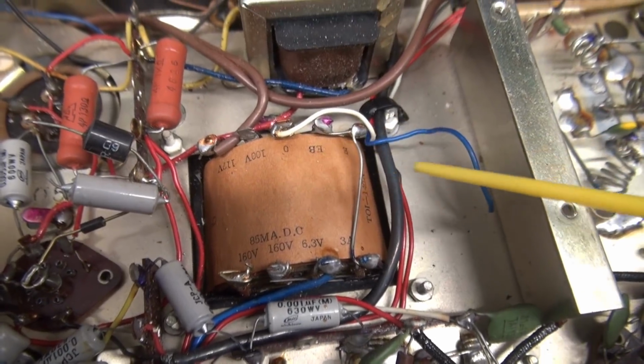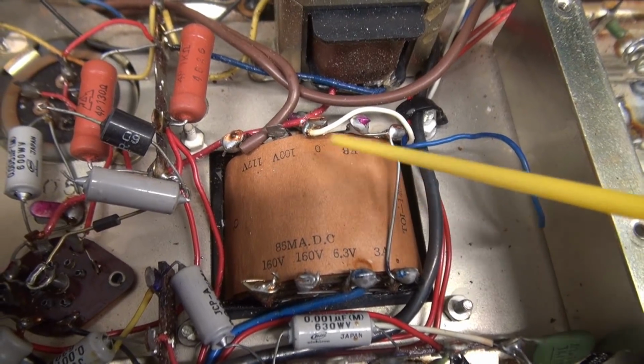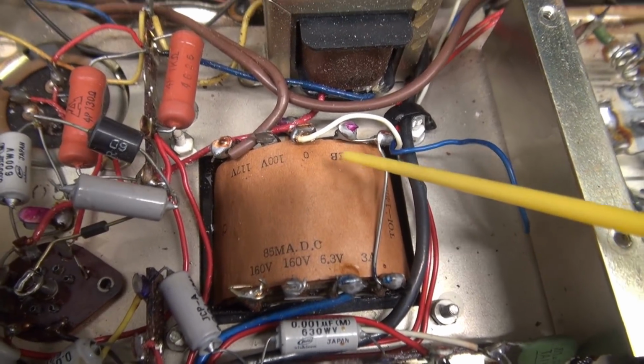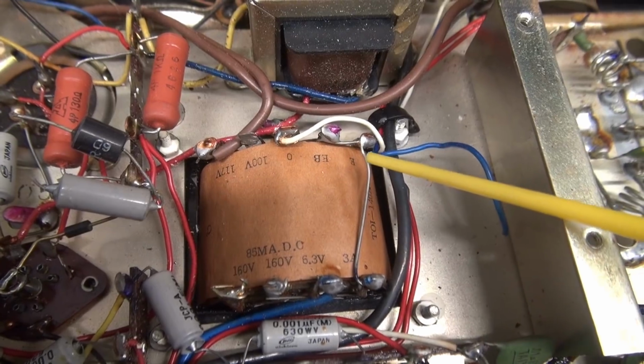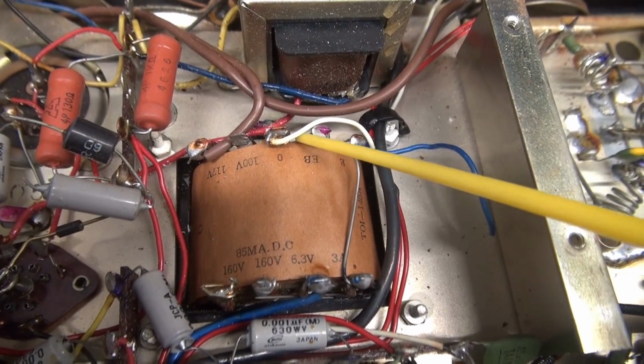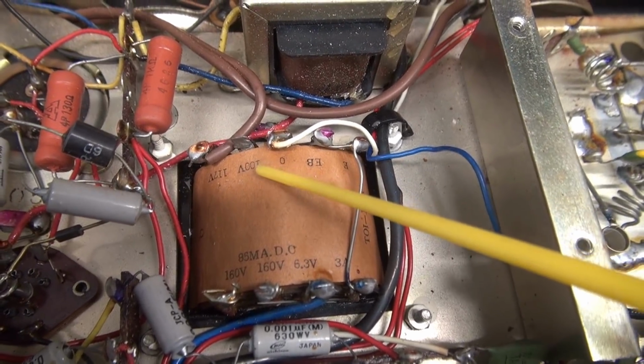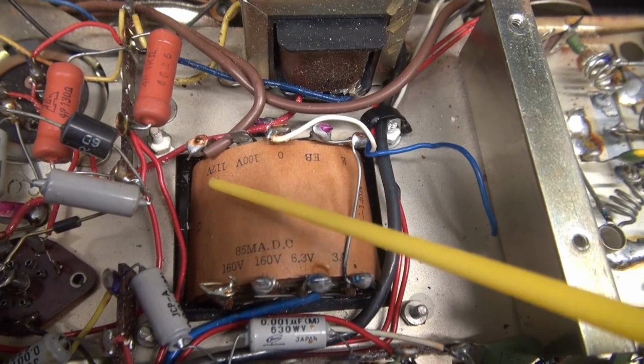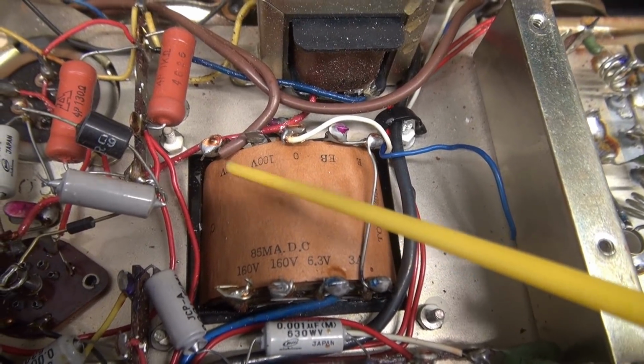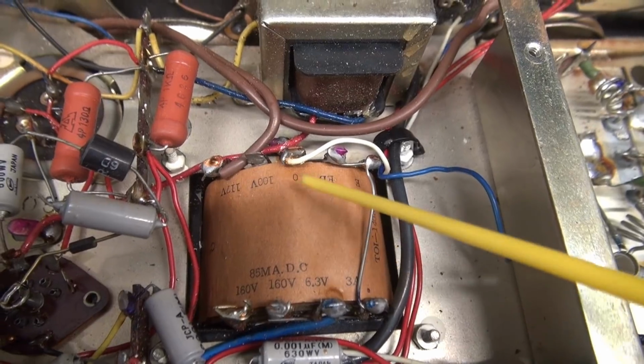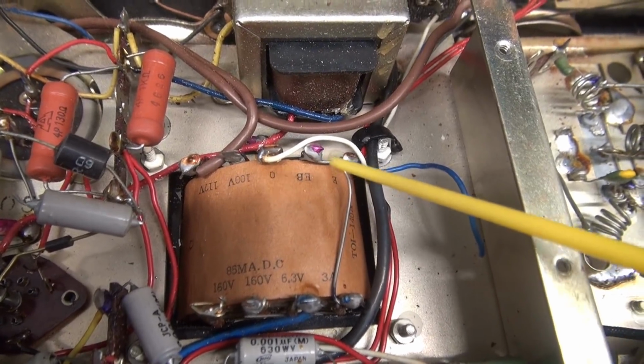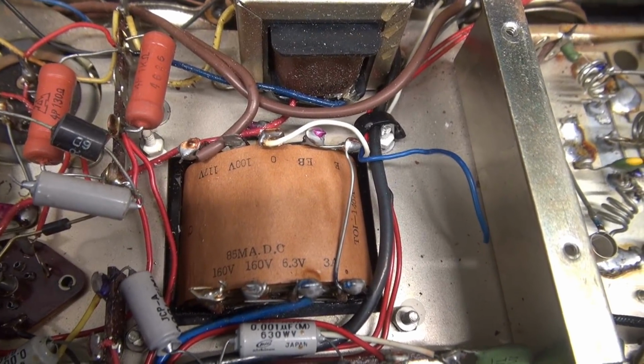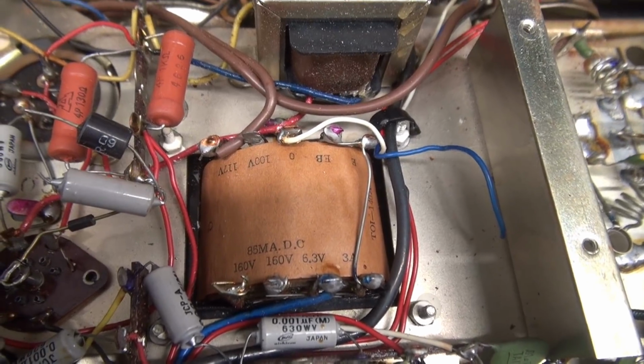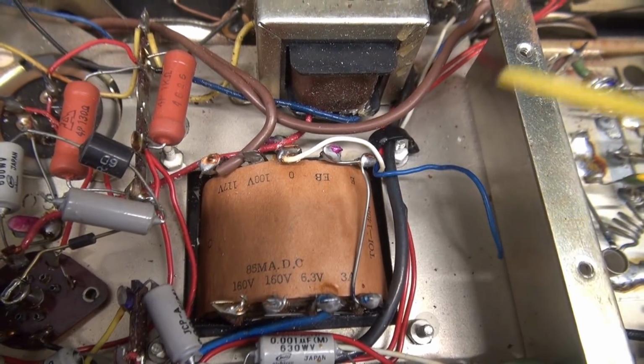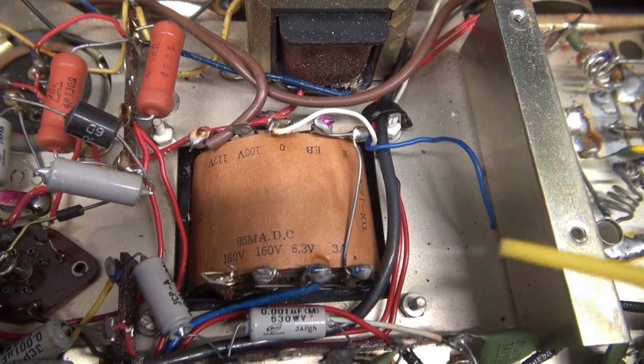I've cut everything out of the way so we can see the terminals of the power transformer. Over here is our primary side: you've got 0, which is your neutral, the 100 volt tap, which isn't used, and the 117 volt tap, which was used back in the day. Obviously our line voltage these days is around 123 volts, which isn't going to hurt anything — the transformer will just put out a little more voltage on the secondaries.